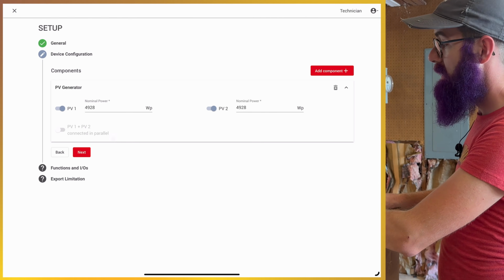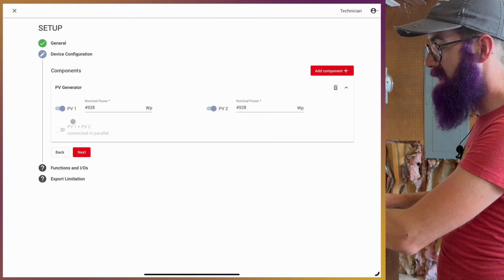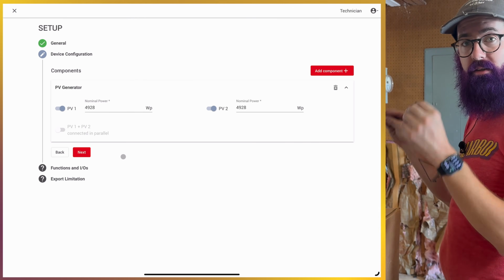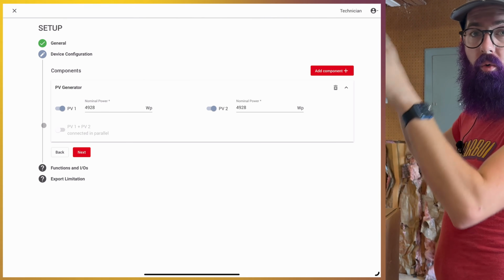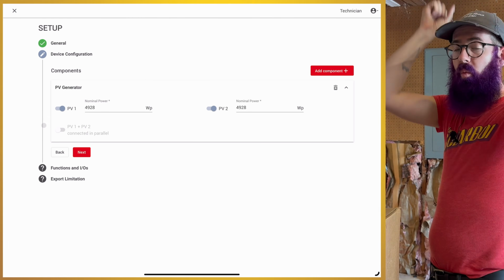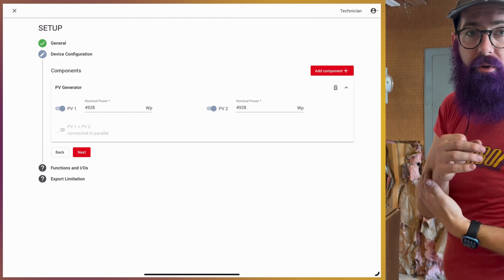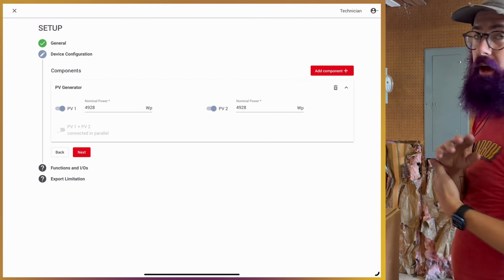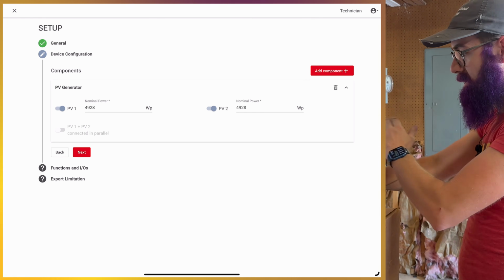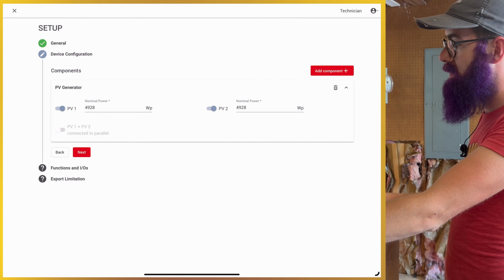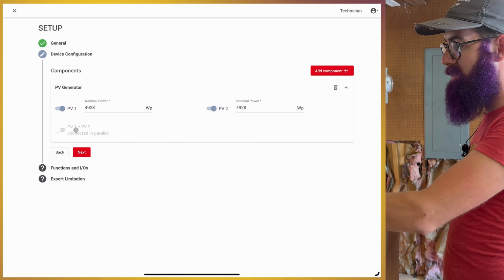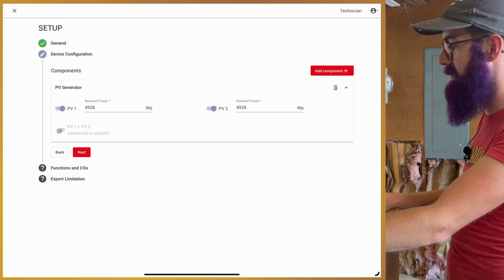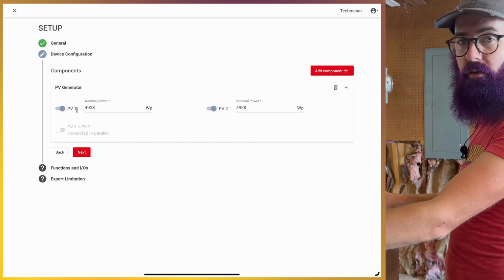Just a note here, if you have connected your PV1 and PV2, your MPPTs, as a whole unit, like if you have one wire coming down from your roof that has multiple strings on it and you need to cross them across all your MPPTs, you need to select PV1 plus PV2 connected in parallel. Otherwise, you're gonna have issues.